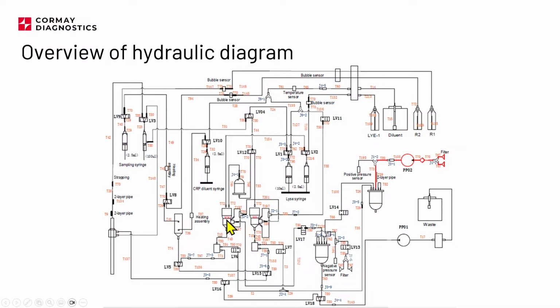What we are seeing here, one more time: WBC chamber, RBC chamber. Impedance channel WBC, RBC channel WBC, RBC channel impedance, right? On the WBC, we also have the bracket, which contains the hemoglobin measurement channel. So it will be the green LED and the detector with the filter across the chamber. So it's measuring the absorbance there.